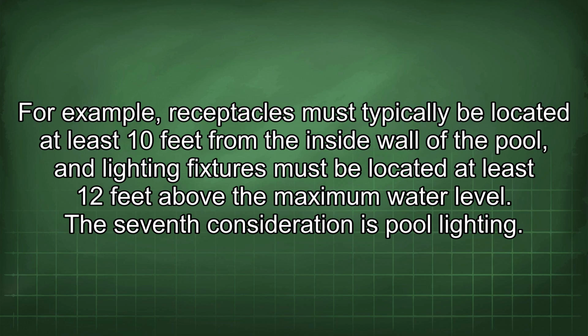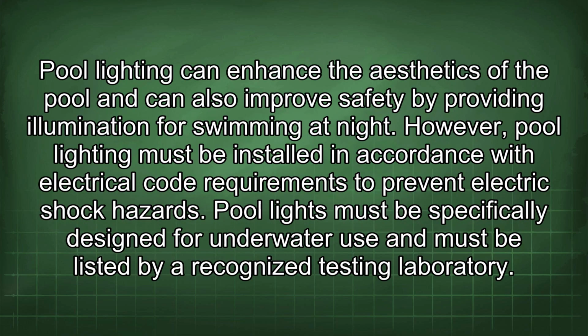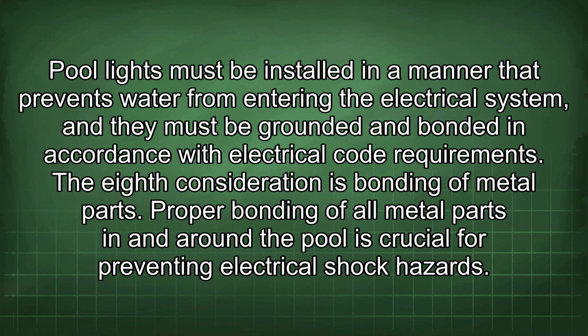The seventh consideration is pool lighting. Pool lighting can enhance the aesthetics of the pool and can also improve safety by providing illumination for swimming at night. However, pool lighting must be installed in accordance with electrical code requirements to prevent electric shock hazards. Pool lights must be specifically designed for underwater use and must be listed by a recognized testing laboratory. Pool lights must be installed in a manner that prevents water from entering the electrical system, and they must be grounded and bonded in accordance with electrical code requirements.